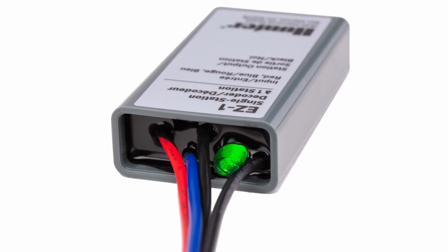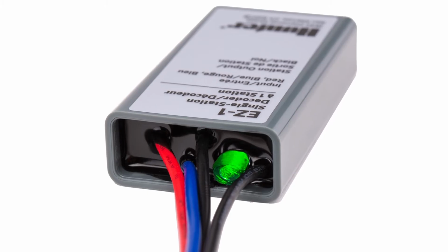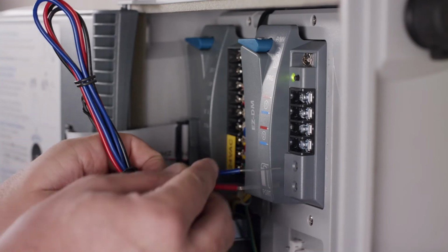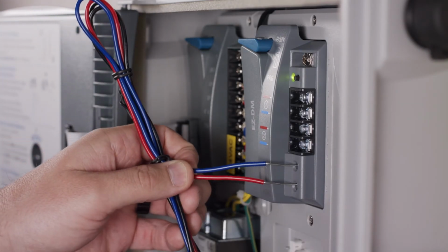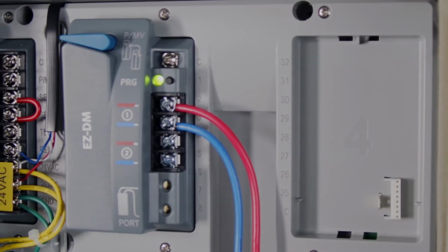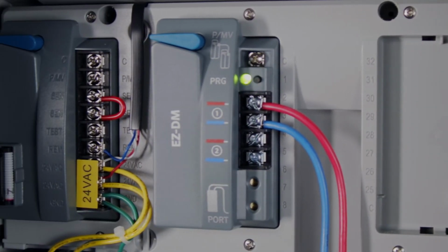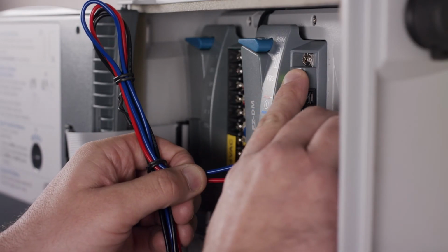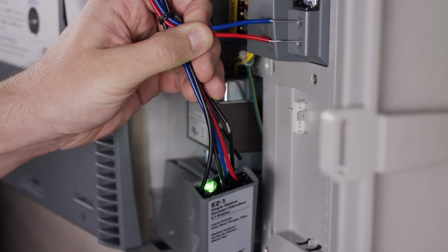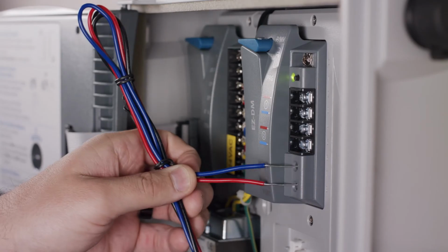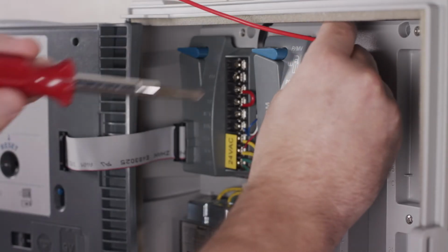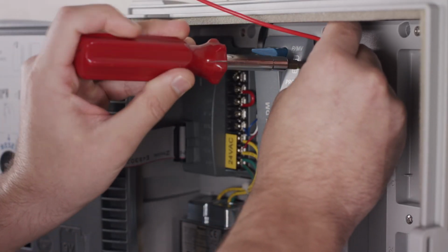To program a decoder as a pump master valve, simply insert the red and blue wires into the programming port without activating any station. The EZDM LED will be a solid green indicating the power is on. Push the PRG button and wait for the decoder light to turn green. It's that easy.